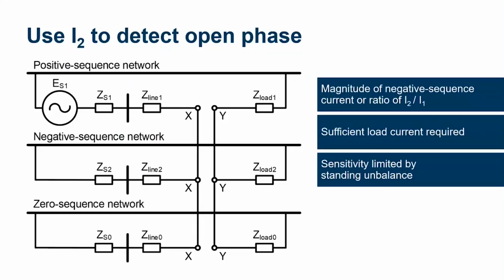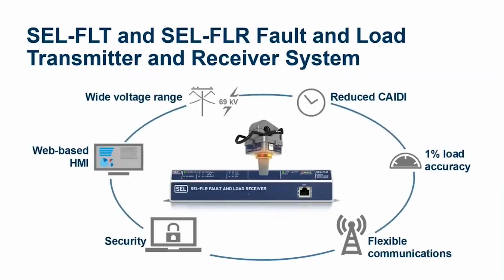So if we have large unbalance already, that's going to limit our sensitivity. But also, if we don't have enough load there, then we're not going to be able to detect it. So this method is better for detection of, say, an open phase condition on your main line or on a heavily loaded lateral.